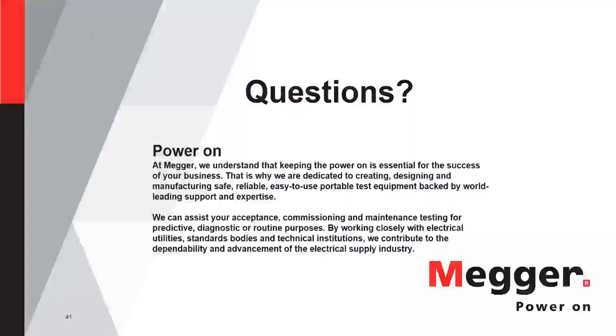Okay, thanks, Volney. Let's move on to the next question. Where are the values of acceptable ripple current and voltage derived from? Is it listed in a standard? Well, it depends. The ripple limits come out of the IEEE 450 and 1188 standards, and basically the limitation is 5 amps of ripple current per 100 amp hour capacity of the cell. That is generally because of the heating effects that can build up over time. Now, in reality, if you're using a substation application, exceeding that amount would typically be a sign of a bad charger. But in other applications like telecom, you could see that sort of noise from the load side as well.